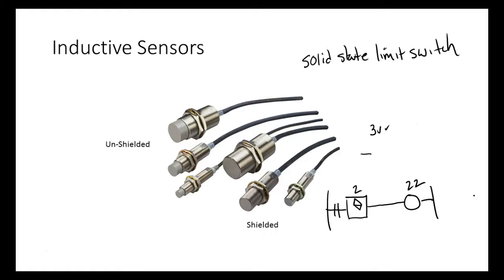Solid state limit switches will drop a voltage, but they operate through the load. They drop very little voltage. On our AC sensors, they drop about 4 volts, but since it's 120 volts AC, that still leaves 116 volts to operate the relays and stuff.